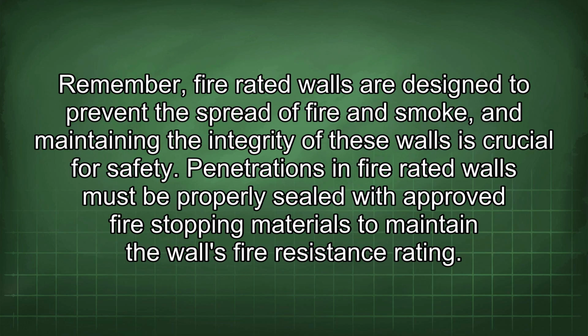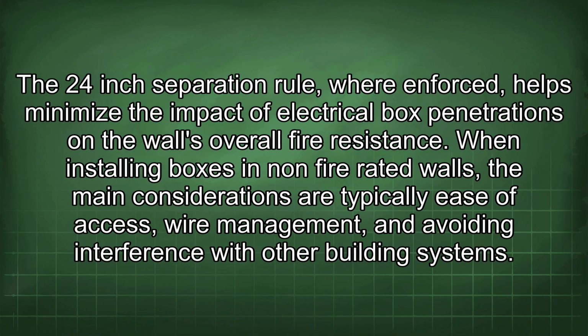Remember, fire-rated walls are designed to prevent the spread of fire and smoke, and maintaining the integrity of these walls is crucial for safety. Penetrations in fire-rated walls must be properly sealed with approved fire-stopping materials to maintain the wall's fire resistance rating. The 24-inch separation rule, where enforced, helps minimize the impact of electrical box penetrations on the wall's overall fire resistance. When installing boxes in non-fire-rated walls, the main considerations are typically ease of access, wire management, and avoiding interference with other building systems.